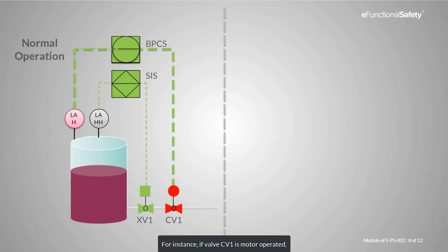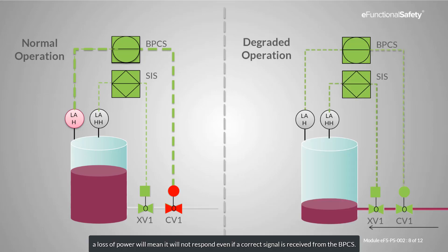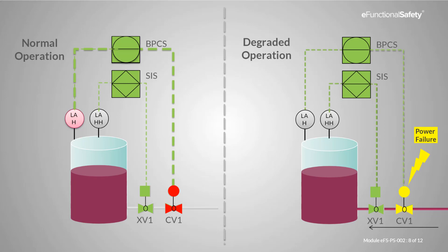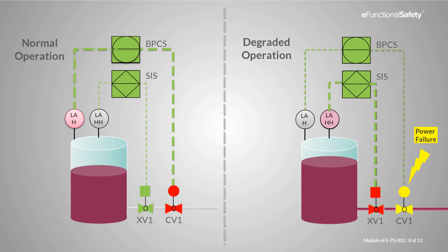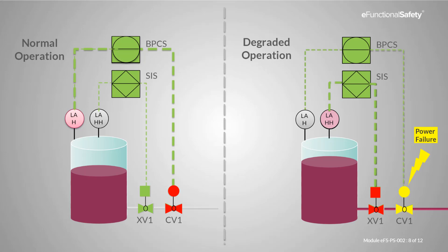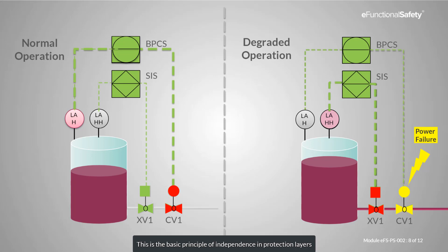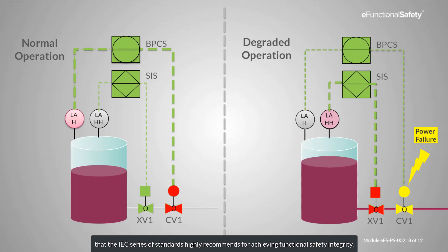For instance, if valve CV1 is motor operated, a loss of power will mean it will not respond even if a correct signal is received from the BPCS. However, the function from sensor LAHH through the SIS logic solver to separate valve XV1 is completely independent, and the spring-actuated valve will stop the flow into the tank even on complete power loss. This is the basic principle of independence in protection layers that the IEC series of standards highly recommends for achieving functional safety integrity.